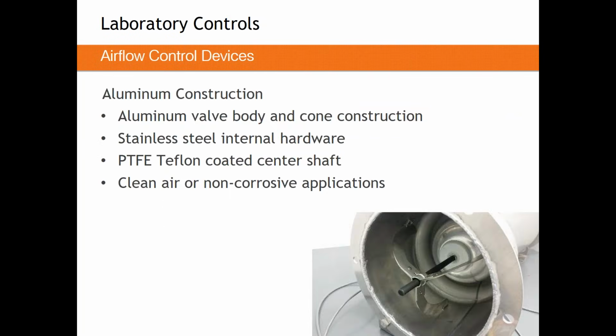So let's move on a little bit here to the valve construction. You all know probably more than I do about VAV box and their construction, so we're going to leave them out here. But for high accuracy terminals and Venturi valve, they are generally always aluminum bodies. They're always a spun aluminum body. Some of the hardware internal to the valve, so that shaft assembly you see internal and some of the mounting hardware, that will be stainless steel. And the internal center shaft will be a Teflon coating. Teflon is extremely smooth and it's a great bearing surface, and that's why it's actually used here.